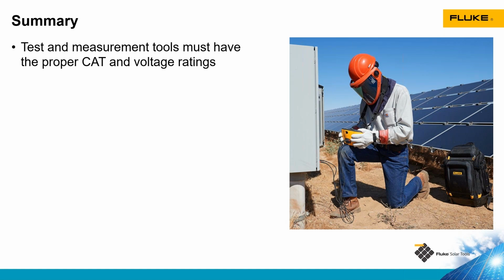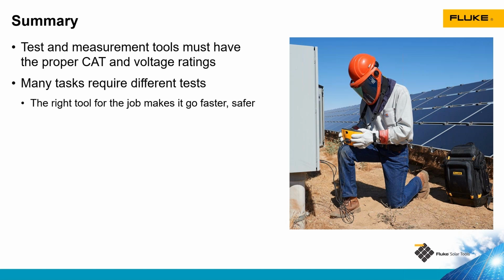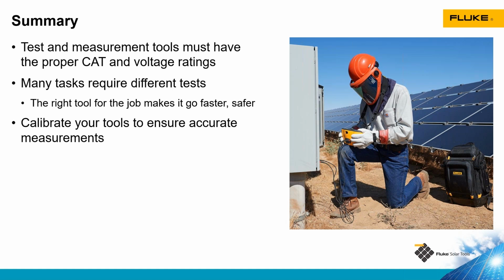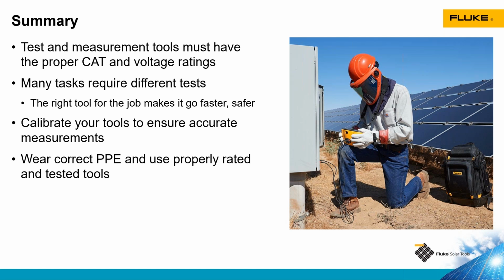Okay, to summarize, we need to make sure that whatever tool we're selecting to do our testing has the proper category rating, category 3 on the DC side, category 3 or category 4 on the AC side, and that the voltage rating is above whatever voltage we're going to be testing at. There are lots of different tests done in the solar industry. Fluke makes a tool for every test that's done in solar. So making sure that you have the correct tool makes it easier and makes it a lot safer when you're doing the testing. We need to calibrate our test tools to make sure that they are taking accurate measurements. And finally, we need to make sure that we're wearing the proper personal protective equipment when we're doing our testing.